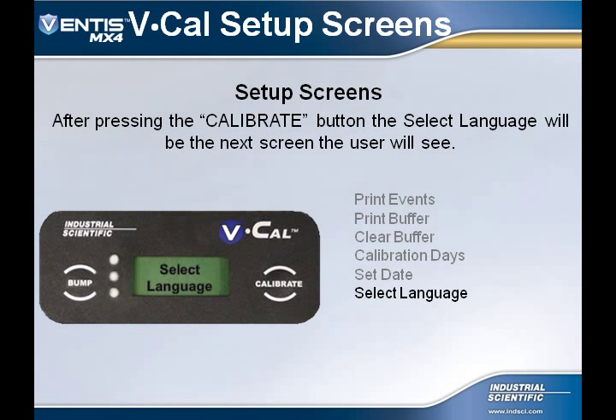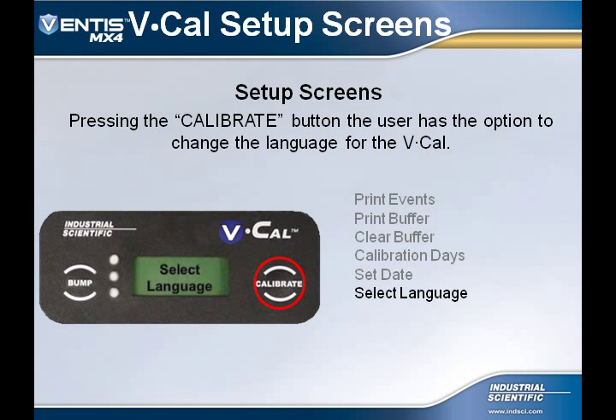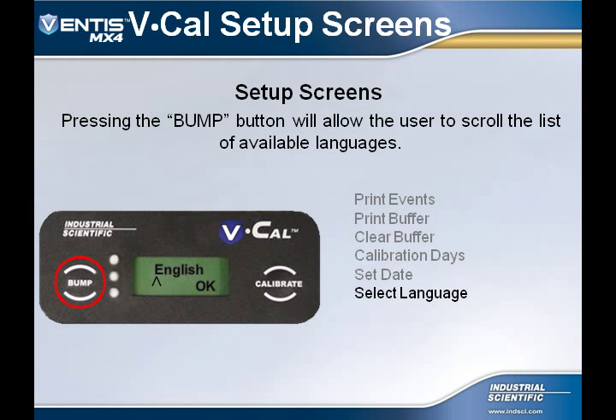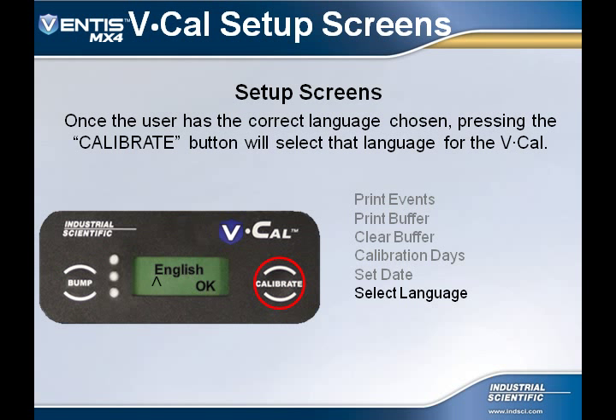The next option is Set Language. This option allows the user to change the language seen on the display of the VCal. Pressing the calibrate button allows the user to select different languages in the VCal. After pressing the calibrate button, the first language you will see is English. Pressing the bump button will allow the user to scroll the list of available languages. Pressing the bump button, the second language is Spanish. Pressing the bump button, and the next language is French. And pressing the bump button will show the last language, which is German. Once the user has selected the correct language, press the calibrate button to enter that language for the VCal.